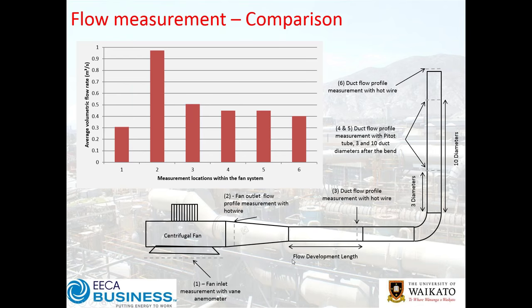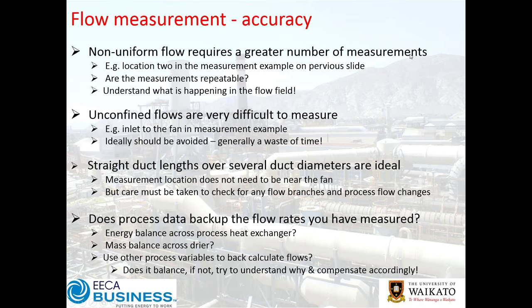The lesson learned is to be very careful where you take your measurement. Sometimes instead of a direct flow measurement, there might be another way — say through heat transfer, where you have a more reliable measurement of water temperature in and out or steam condensed. For non-uniform flow, many more measurements at multiple locations are required, and you need to check repeatability and understand the flow field. Unconfined flows at a fan inlet or open duct exit are very difficult to measure — mostly a wasted effort.